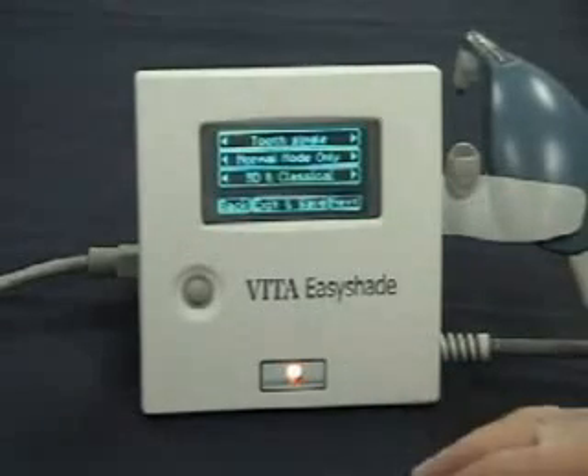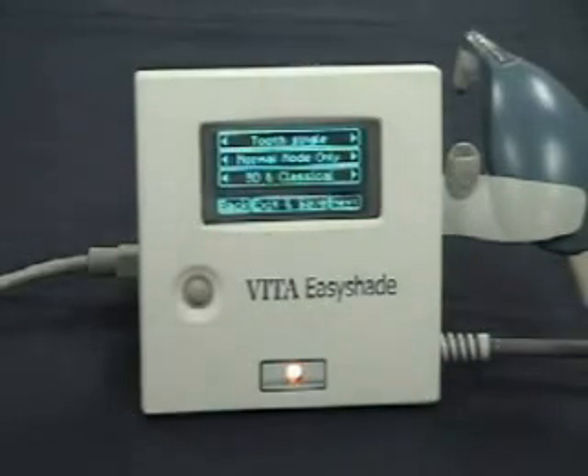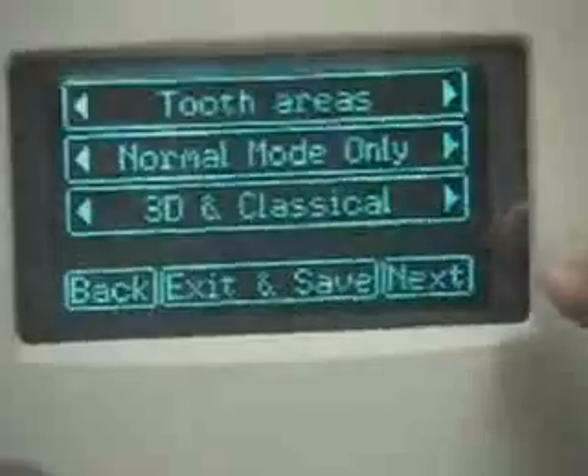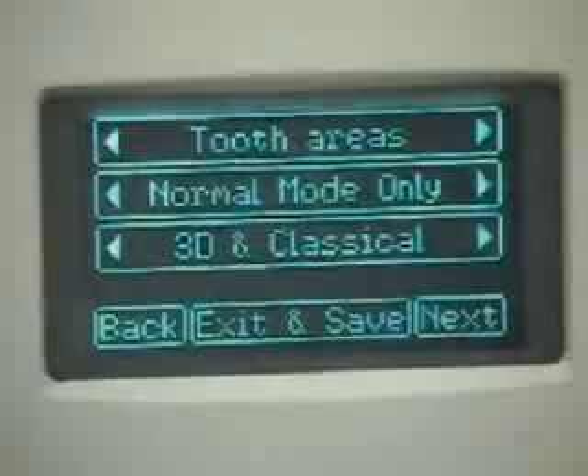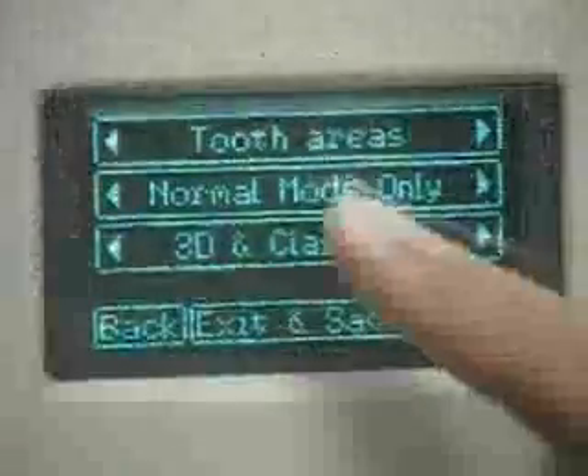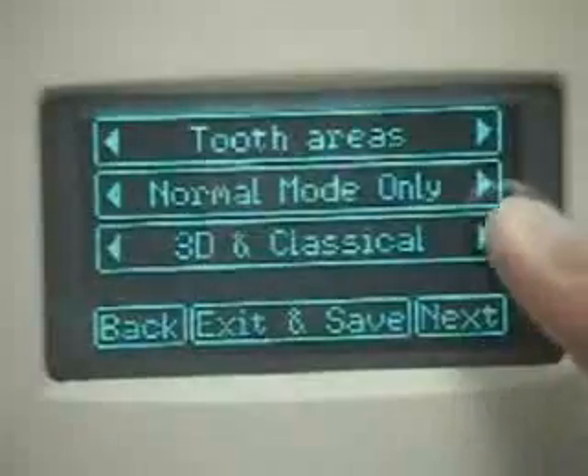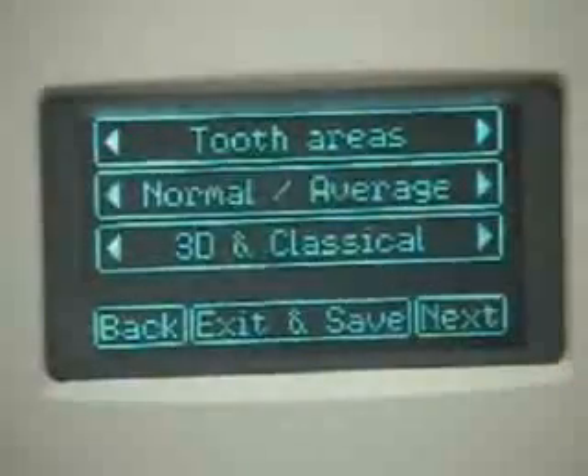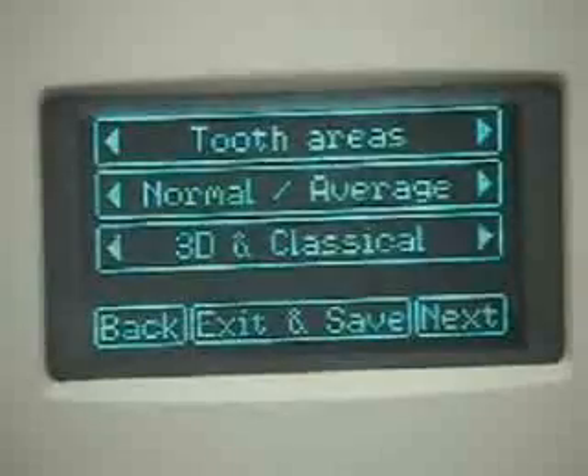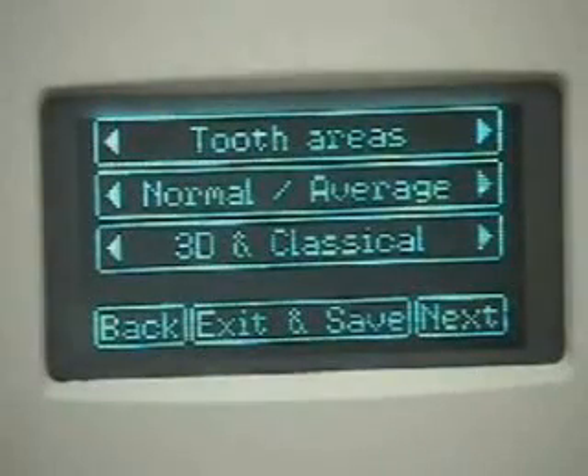On this page, we can change the default menu at power up by navigating the top menu from single to tooth areas or restoration mode. The menu under it denotes normal mode and the choice of normal and average mode. By selecting this, the user will have a constantly displayed, under the normal menu, a secondary option that can be turned on at will to either perform a conventional mode as discussed, but also with the choice of averaging two shades. This mode, when turned on, differs in use by placing the handpiece probe over the various areas of a suspect or confusing tooth dentine area. Then by taking multiple shades, Easy Shade automatically averages and reports the recommended shade result.